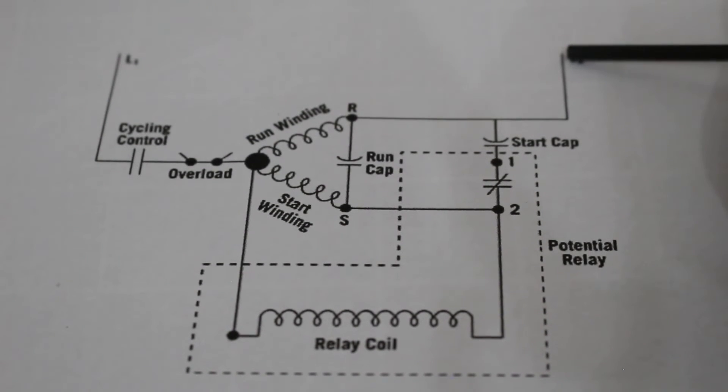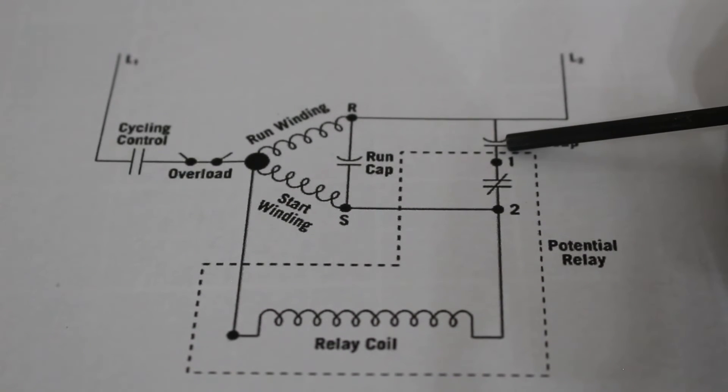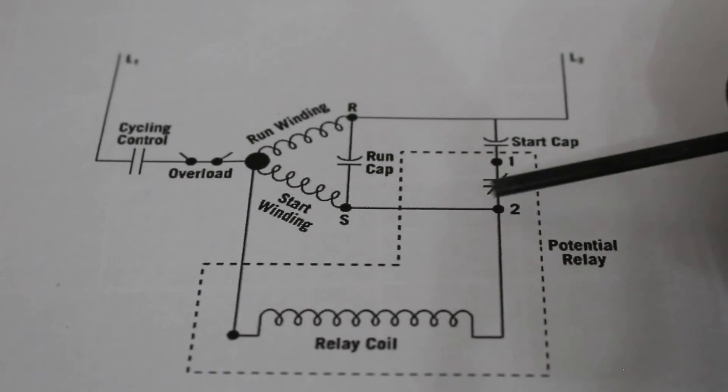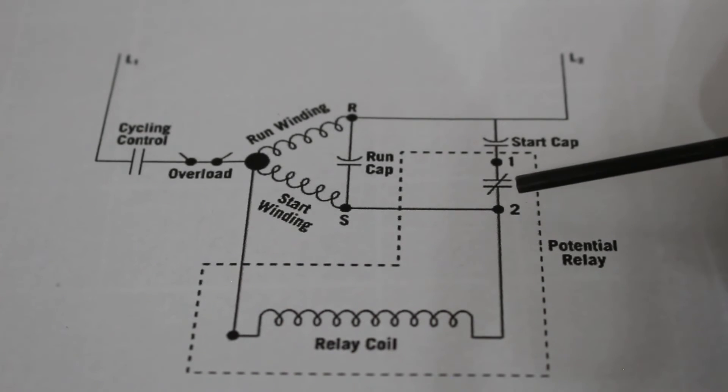So, the whole purpose is to flow electricity to the start cap, help us start. Once we started and reached a certain speed, we're going to get that back EMF. It's going to open these contacts, remove the start winding, excuse me, remove the start cap, and you just run from there.